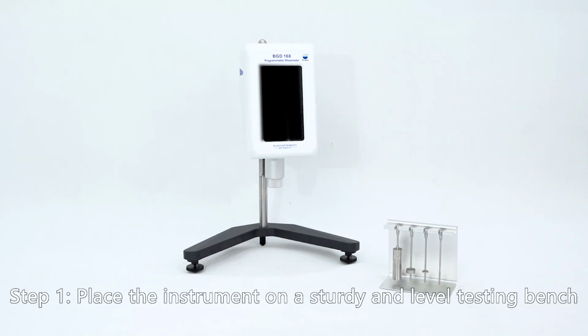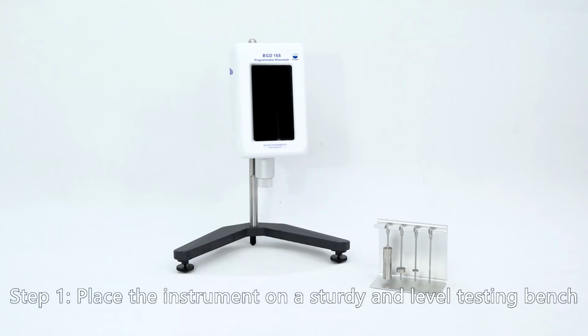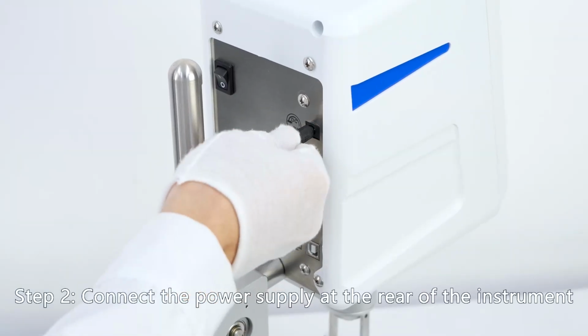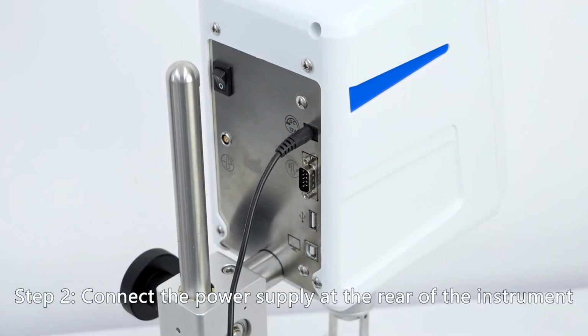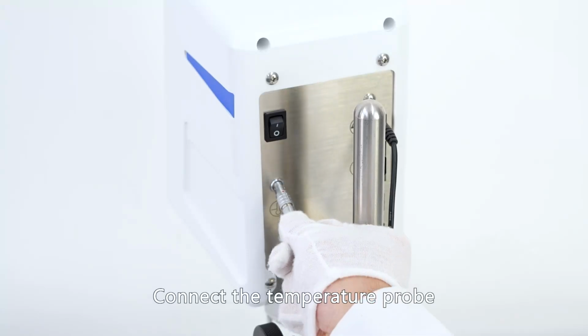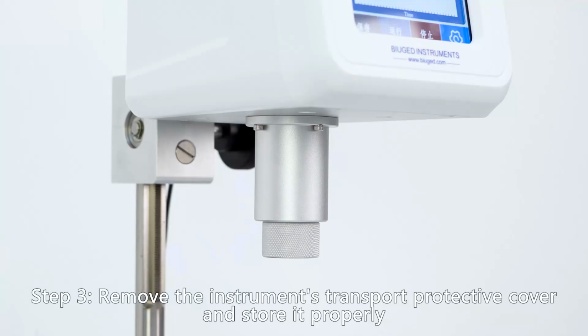Step 1. Place the instrument on a sturdy and level testing bench. Step 2. Connect the power supply at the rear of the instrument. Connect the temperature probe. Step 3. Remove the instrument's transport protective cover and store it properly.